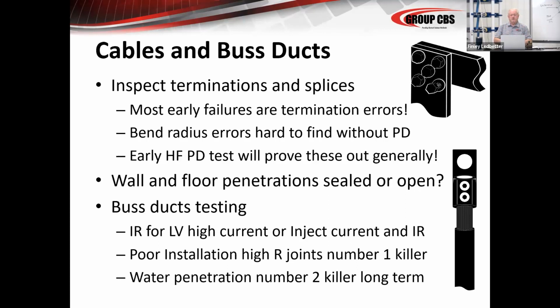And so offline PD testing as part of your acceptance testing is a real smart thing if we have cables involved. That'll find problems with splices and manholes. It'll find termination errors, all the stuff that's usually concealed with a really nice tape job and a lot of duct seal. So lots of times you can't really see it, but it's there, and PD testing is a good way to pick it up early. Are the wall and floor connections supposed to be sealed? Are they supposed to be opened? Always question that.